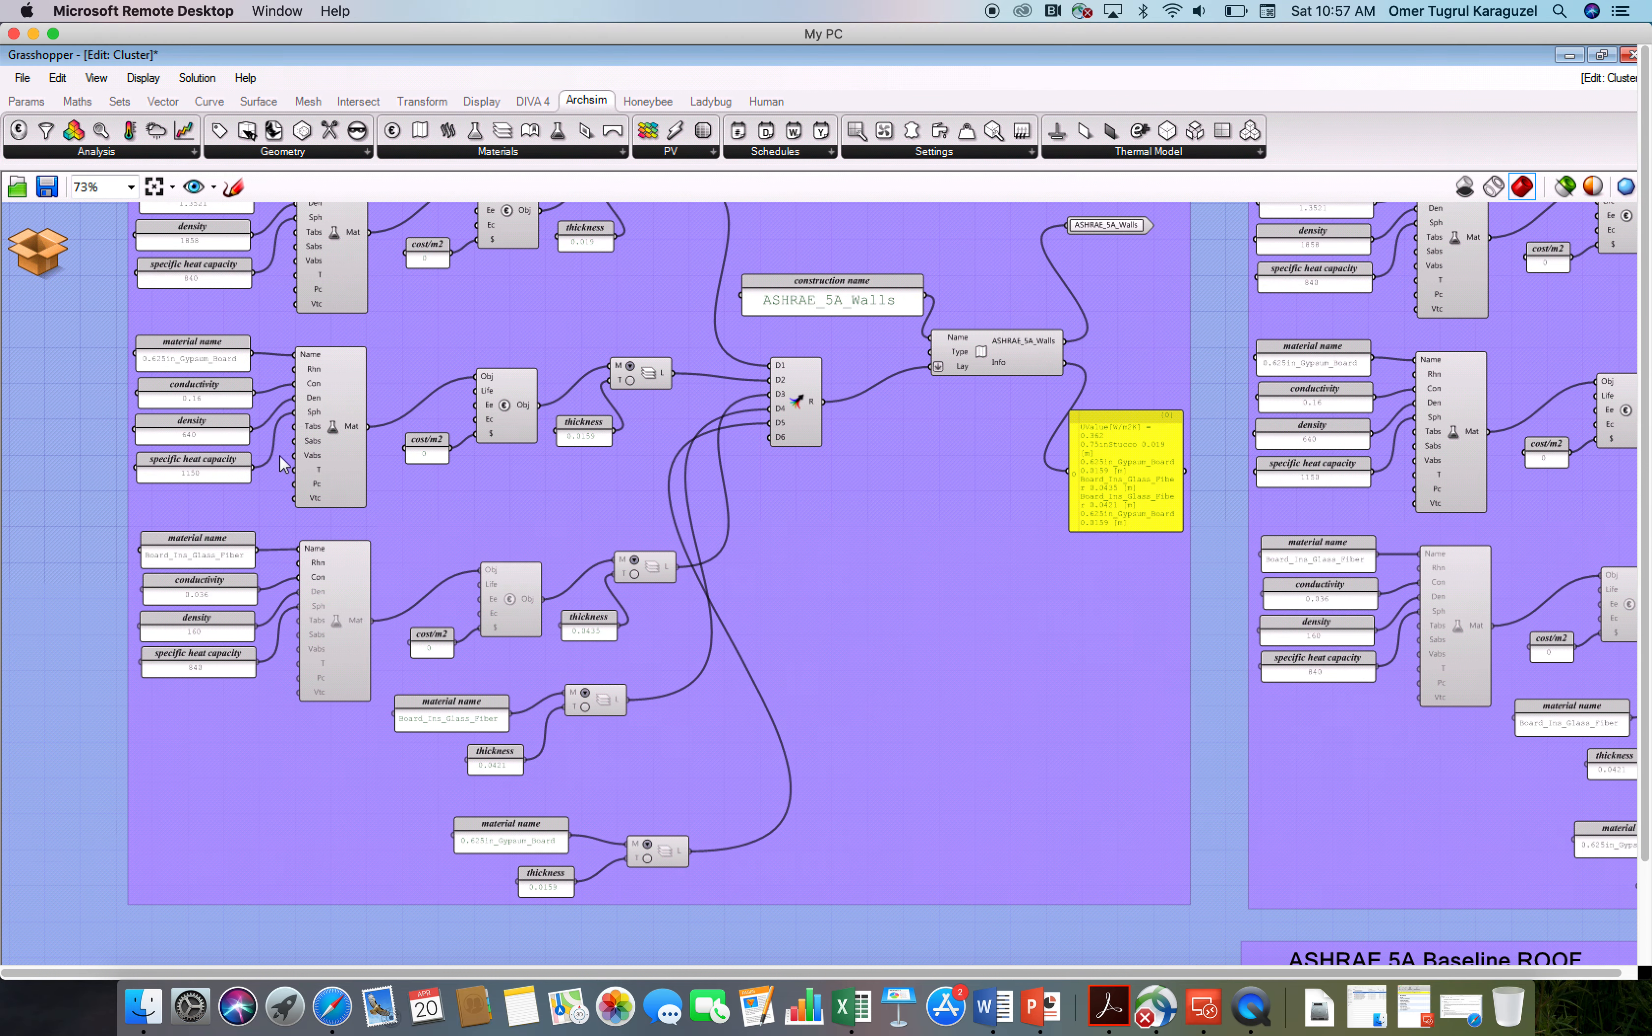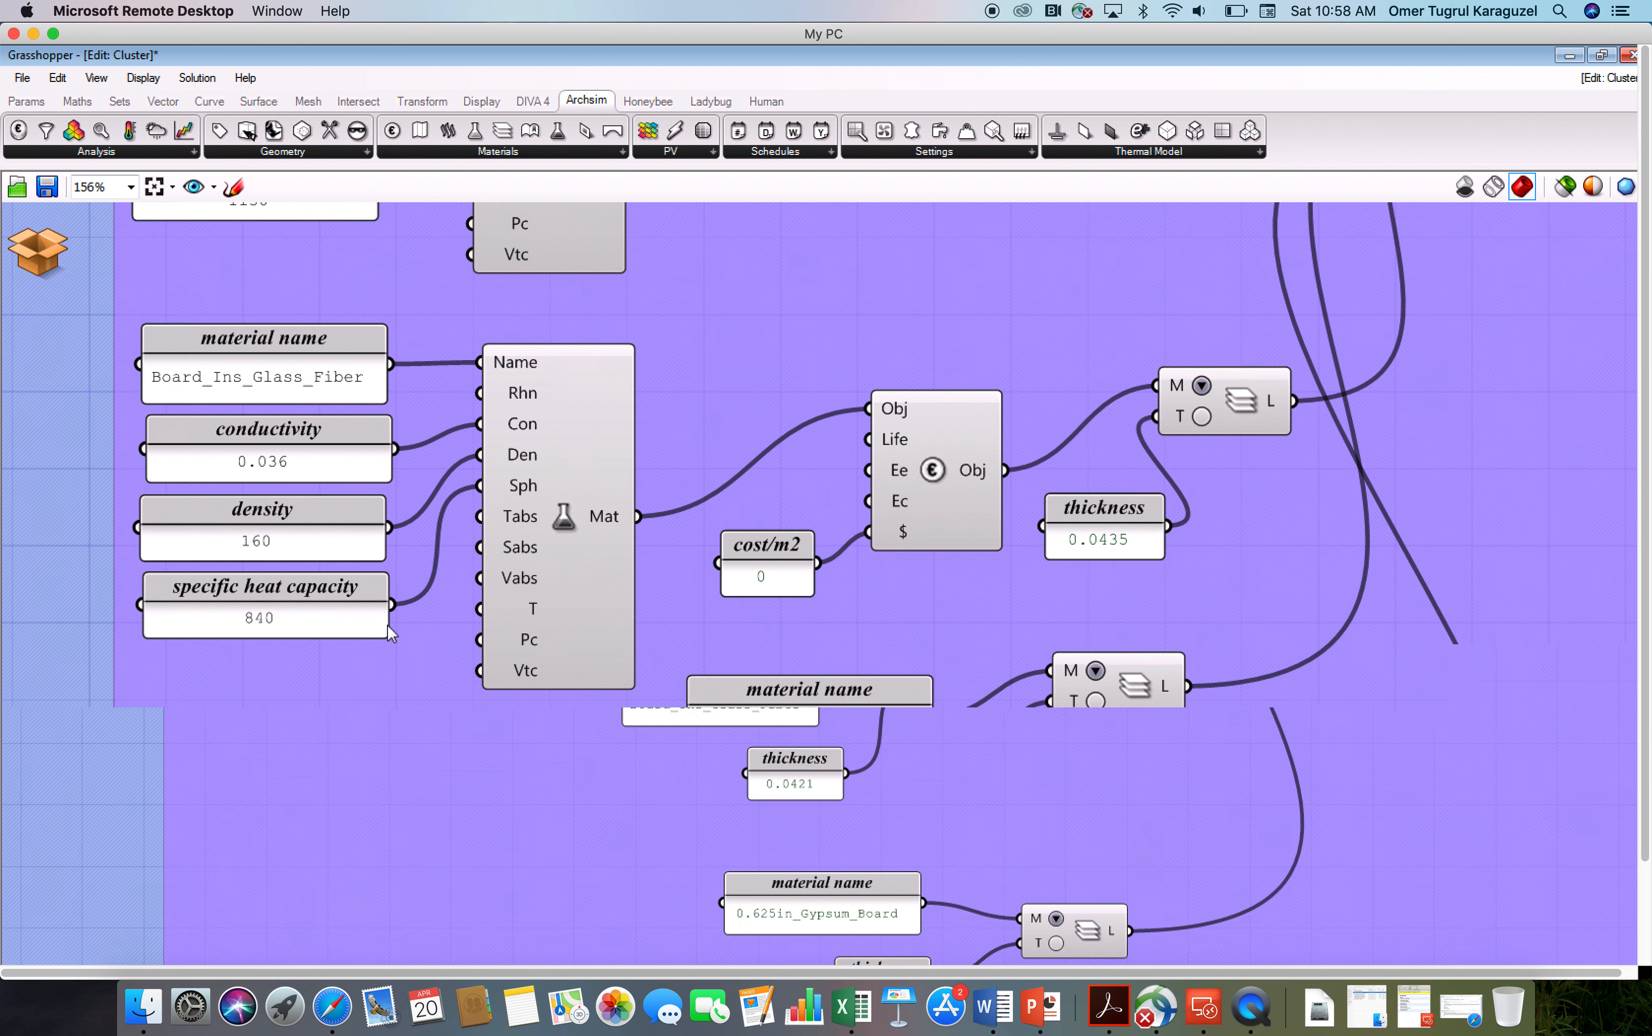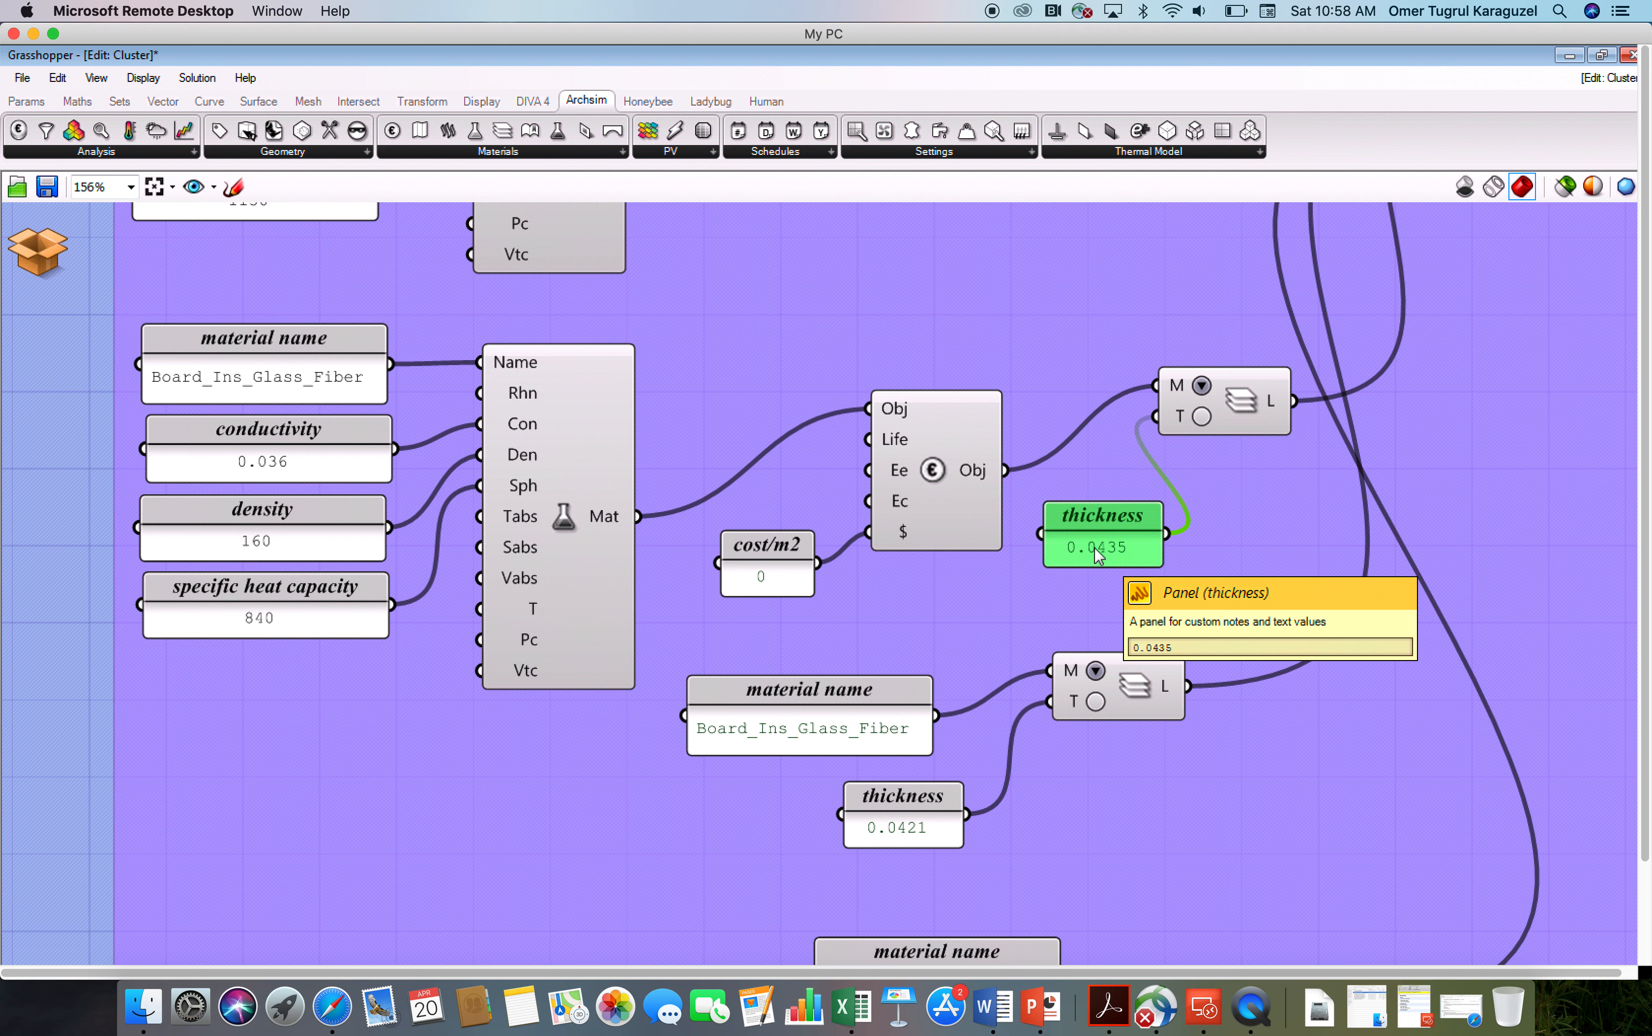So how to do it? The quickest way is to keep all the material layers the same, but just focus on the insulation material layer. Now I am zooming into the insulation material layer. I have board insulation, glass fiber, with certain thermophysical properties like conductivity, density, and specific heat capacity. I'm not going to play with those because these are fundamental properties. But to be able to create the insulation material with the R40 thermal resistance level, I will play with the thickness of this material. I'm going to increase this thickness. But to what level?